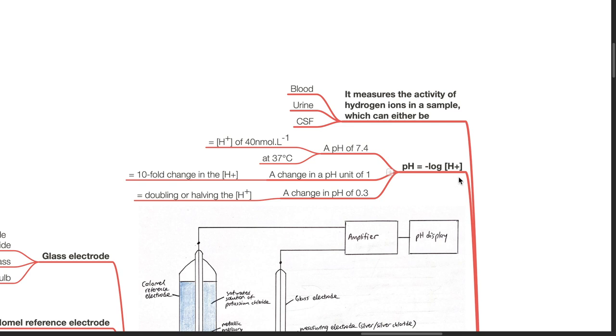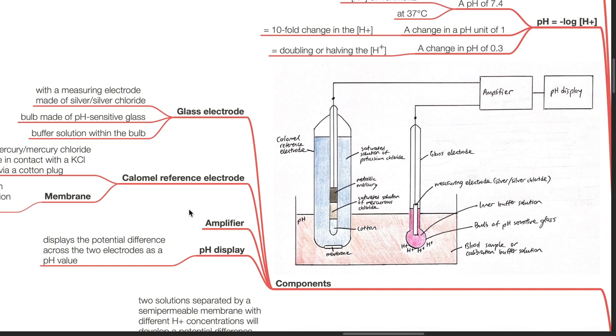The pH electrode measures the activity of hydrogen ions in a sample, which can be blood, urine, or CSF. pH equals negative log of hydrogen ion concentration. A pH of 7.4 equals a hydrogen ion concentration of 40 nanomoles per litre at 37 degrees Celsius. A change of 1 pH unit equals a 10-fold change in hydrogen ion concentration. A change in pH of 0.3 equals a doubling or halving of the hydrogen ion concentration. Components include the glass electrode, calomel reference electrode, amplifier, and pH display.